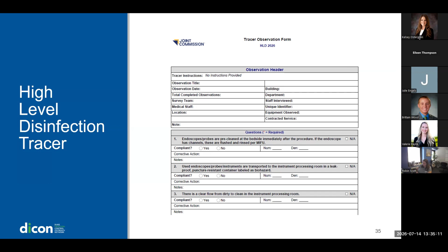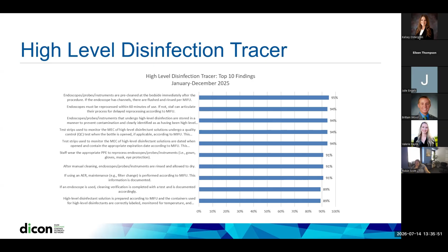The top 10 finding report shown here was from 2025, and these are results from our tracers from last year. As you can see, there are some opportunities identified surrounding AER maintenance, in particular filter changes for our water filters, preparation of high-level disinfection solutions, whether that's Cidex OPA or Maxicide OPA or any one of those other solutions that Brittain shared earlier from our clinic catalog, and then monitoring of minimum effective concentration and documentation of that testing of the high-level disinfectant solution. And then lastly, we also had device pre-cleaning show up on our top 10 findings report last year.